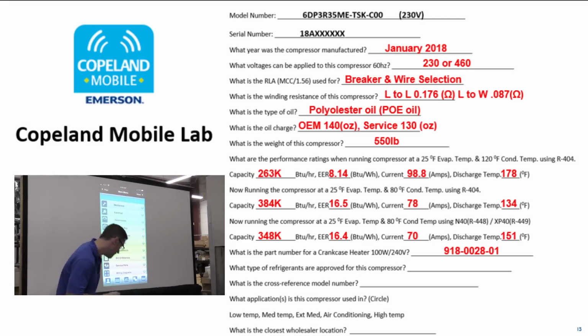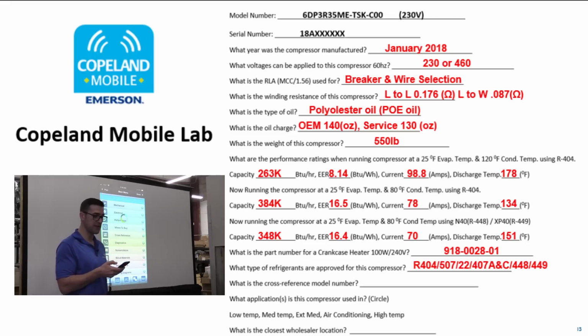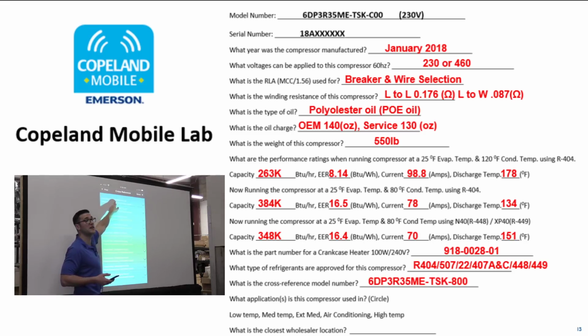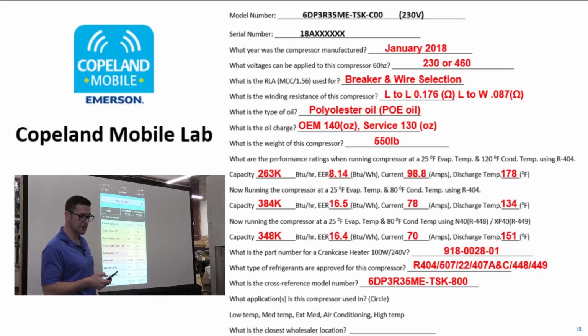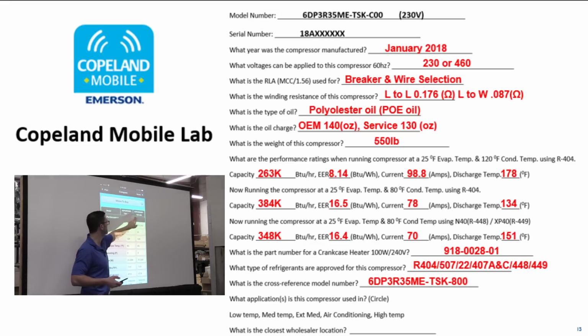You like this. So, next question I had, cross-reference. So you click on cross-reference. And all of a sudden, this is the model that, say, has failed in the field. You know it's failed from an issue. This is the part number, right? The model number of the new compressor. So you just click on the model number, and it'll give you all the differences, right? These ones are the exact same compressor. Just see how the bill of material is different? This is a 100 bill of material. That's an OEM compressor. This is an 800 bill of material. This is a service compressor.